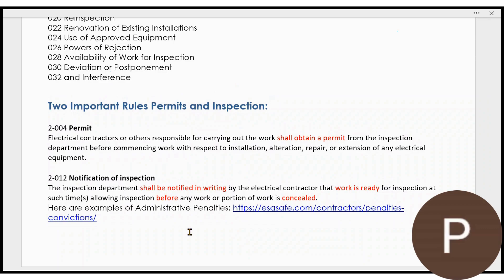First one: make sure you obtain a permit. The person responsible for carrying out the work — if you are an electrical contractor who is legally responsible and permitted to carry out this work — must obtain a permit from your inspection department before commencing the work. That doesn't mean you start installing, start an alteration, or perform a repair and then get a permit. That means you stop, you get a permit. Once you obtain the permit, then you can install, alter, repair, or do an extension of that electrical equipment. You do not work without a permit.